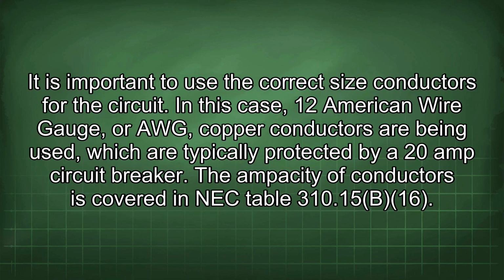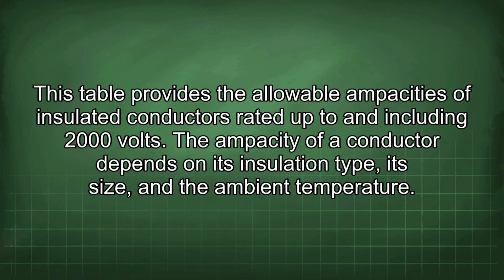It is important to use the correct size conductors for the circuit. In this case, 12 American Wire Gauge, or AWG, copper conductors are being used, which are typically protected by a 20 amp circuit breaker. The ampacity of conductors is covered in NEC Table 310.15(B)(16). This table provides the allowable ampacities of insulated conductors rated up to and including 2000 volts.